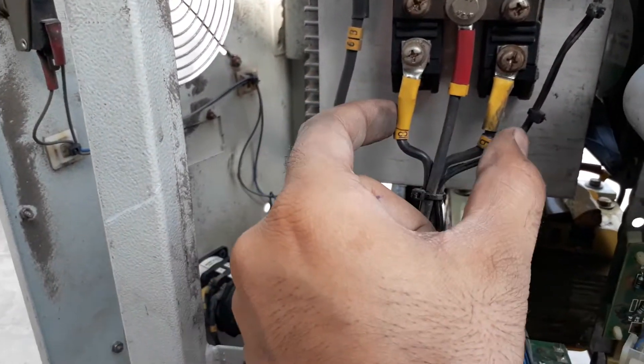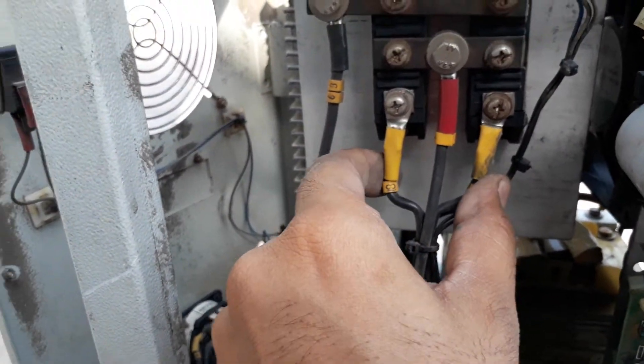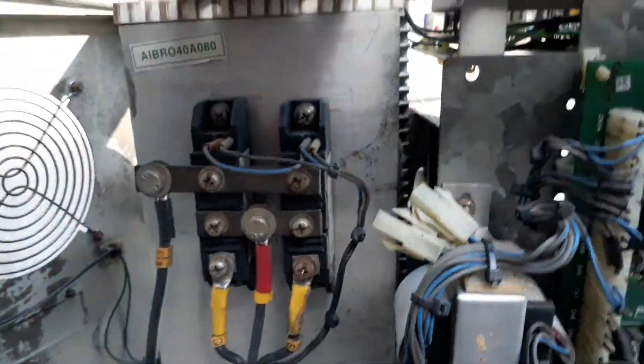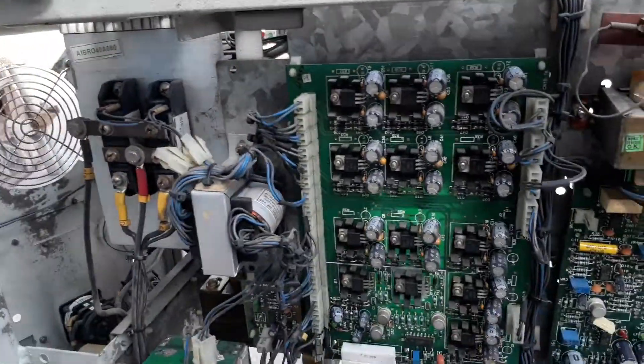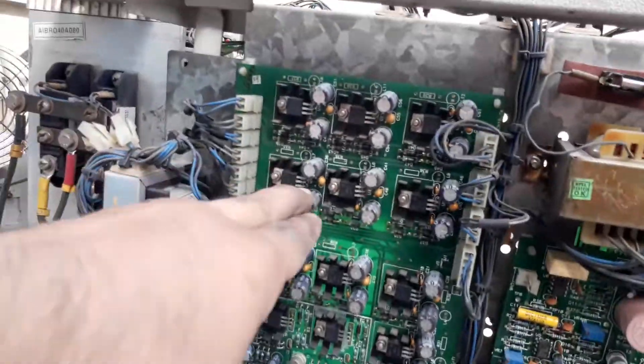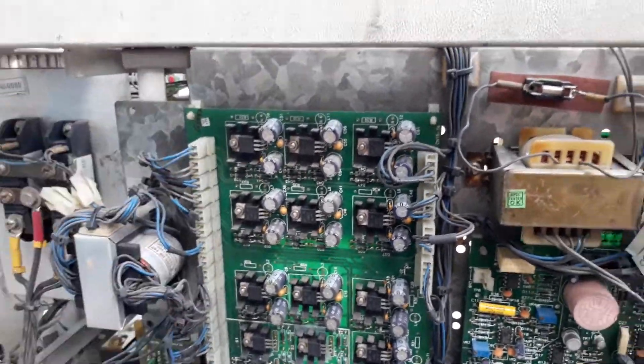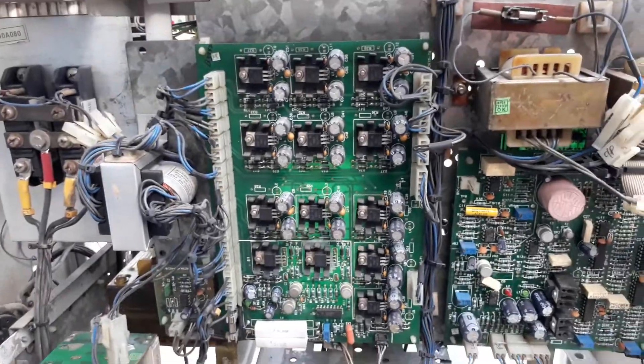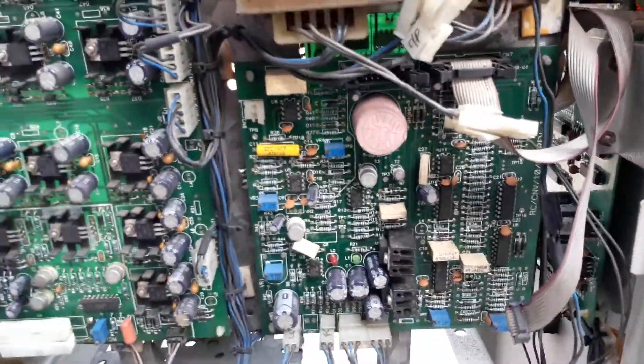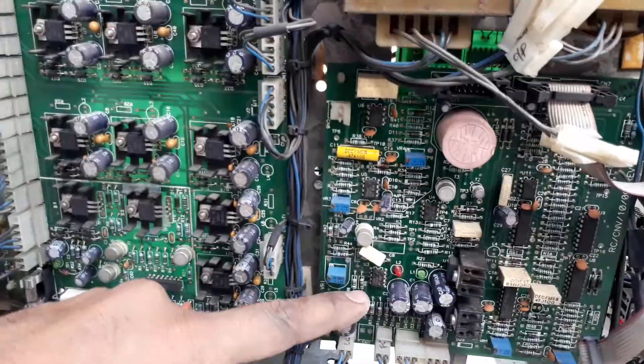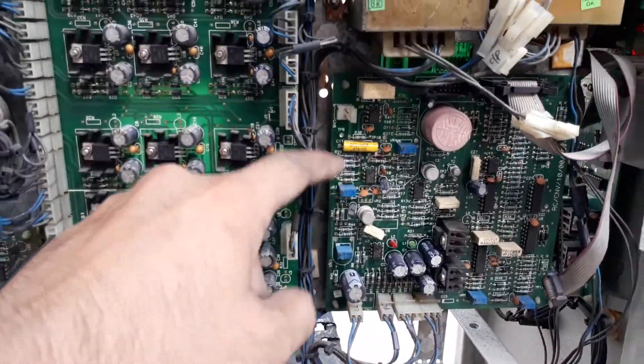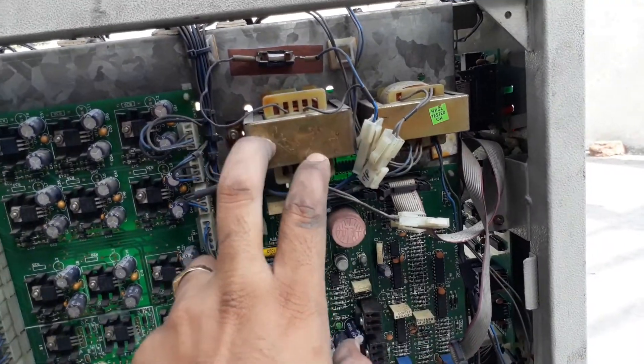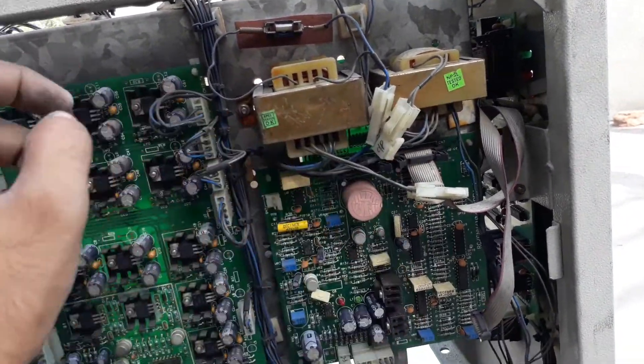These two provide the step-down voltage to this SCR. They control the output from the SCR. This section has the information of all the voltages. It is a firing card or SCR firing card. It fires the SCRs, and these two transformers check the input and output voltage and give signals to this card.